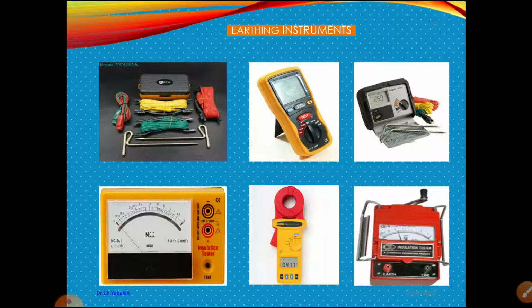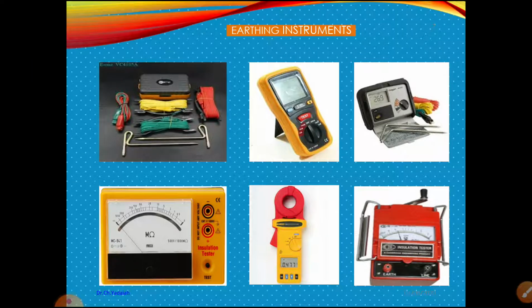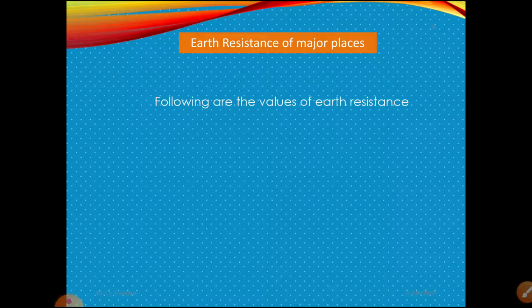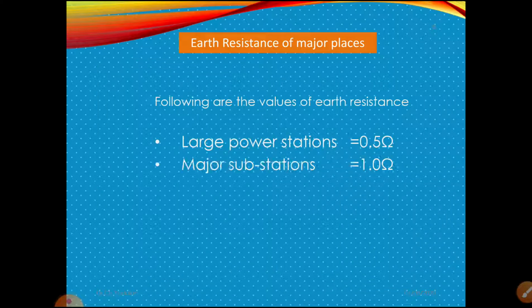Okay, so let us calculate. What is the value? Remember, for large power stations, for example thermal power stations like NTPC, and hydropower stations like Nagarjuna Sagar, Ramagundam, and Kottagudam power plants, the total substation or large power station earth resistance must be nearly 0.5 ohms, very low resistance is required. For major substations, it may be allowed up to 1 ohm, and for smaller substations like 33 by 11 kV substations, we use 2 ohms. In all other cases, like domestic equipment and so on, we use 5 ohms. Dear students, remember this, it is very important for competitive exams.